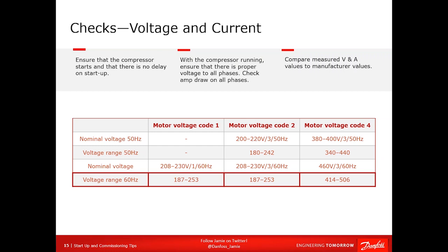Also check it when it's running. Picture a car battery. You can measure 12 volts on a car battery that's got bad cells inside, but as soon as you put a load on, the voltage goes in the toilet. Well, the same can happen in here. If you put a load on an already strained system, you can see your voltage drop to very low levels. Make sure you measure in both cases. If it's 3 phases, measure all 3 phases. If it's single phase and your voltage sucks, try looking at some of the other phases, but either way you look at it, it has to be corrected.